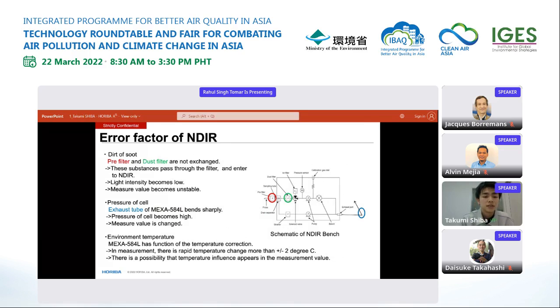Thank you. Next, I'd like to introduce the error factors of NDIR. There are various factors that cause NDIR error, but here we will introduce three. The first is dirt, such as soot. If you don't replace the pre-filter on the probe or the dust filter on the device, impurities such as soot are more likely to enter the detector. If the inside of the detector becomes dirty, the amount of infrared light will decrease. If the measurement is performed in such a state, the measured value may become unstable, resulting in an error in the measured value.